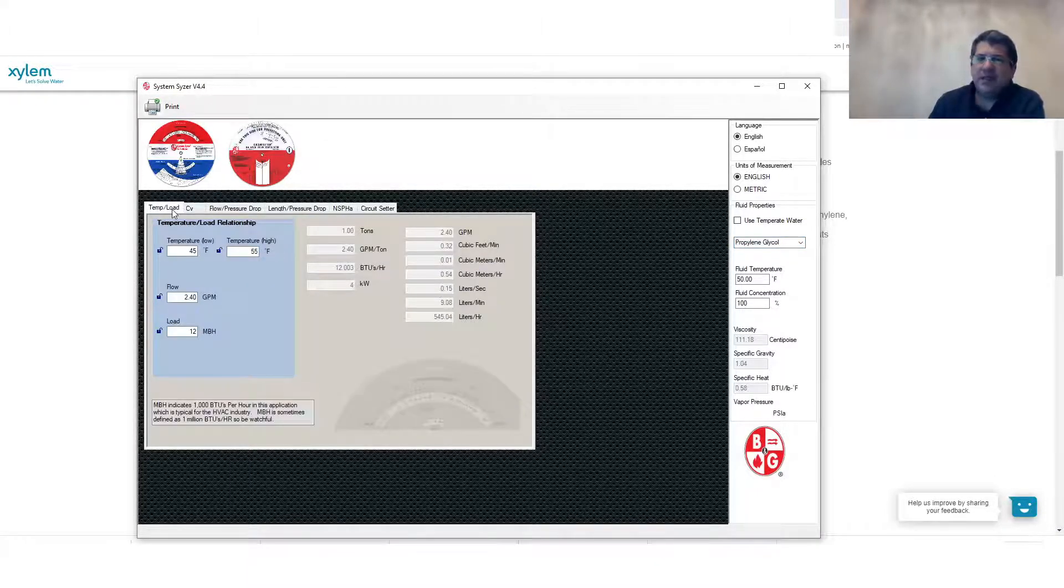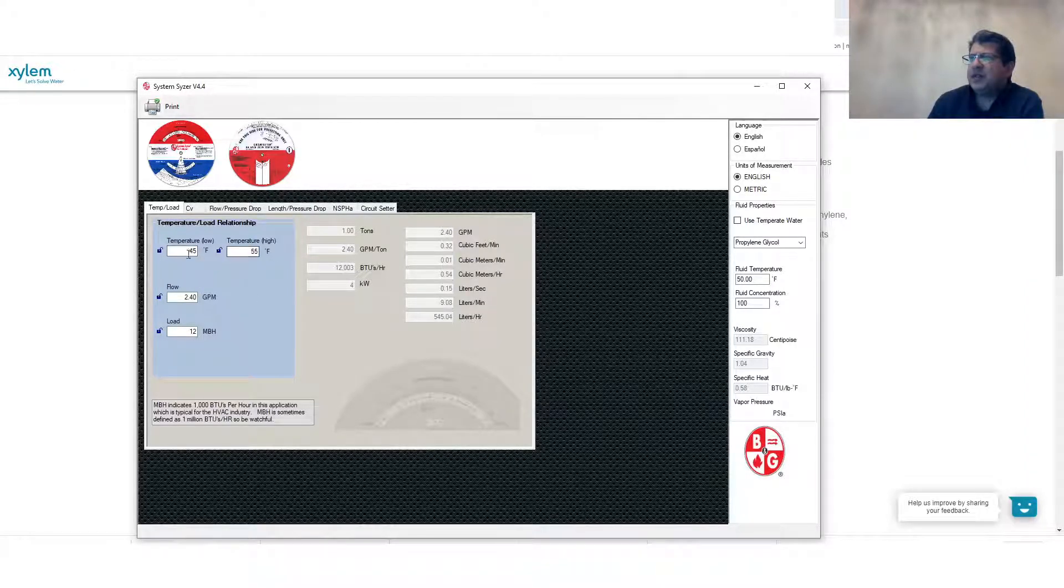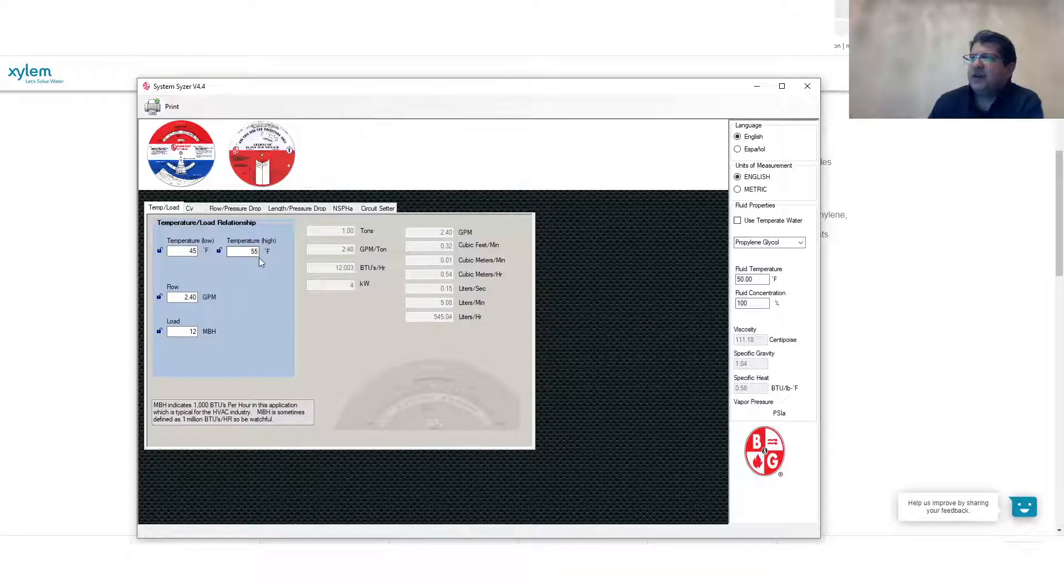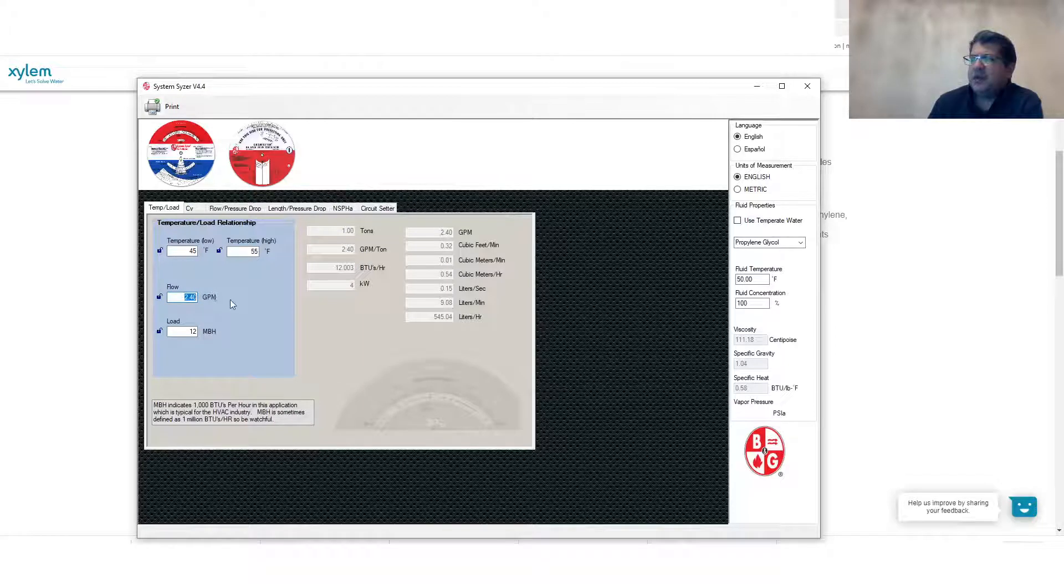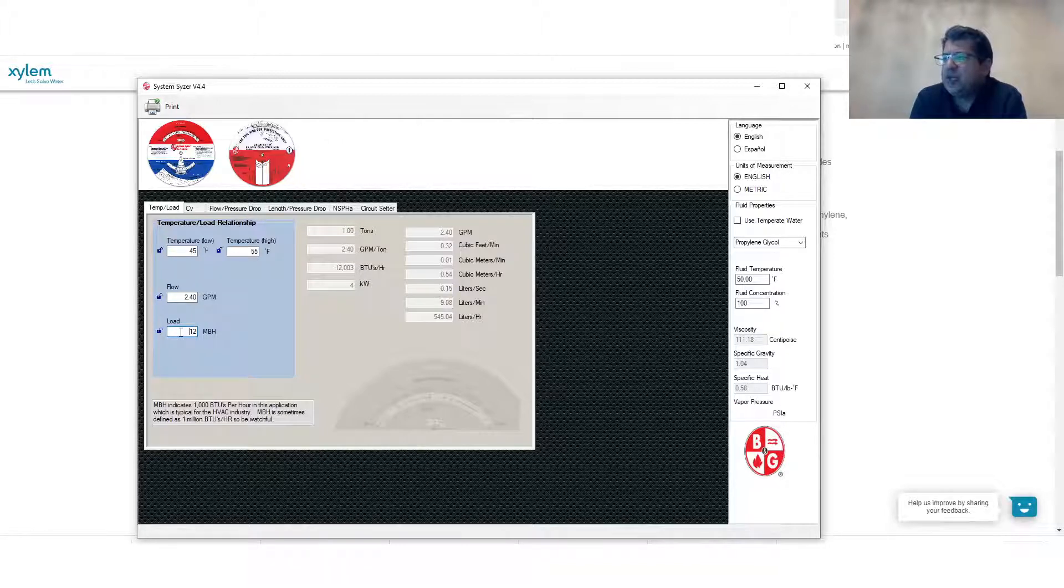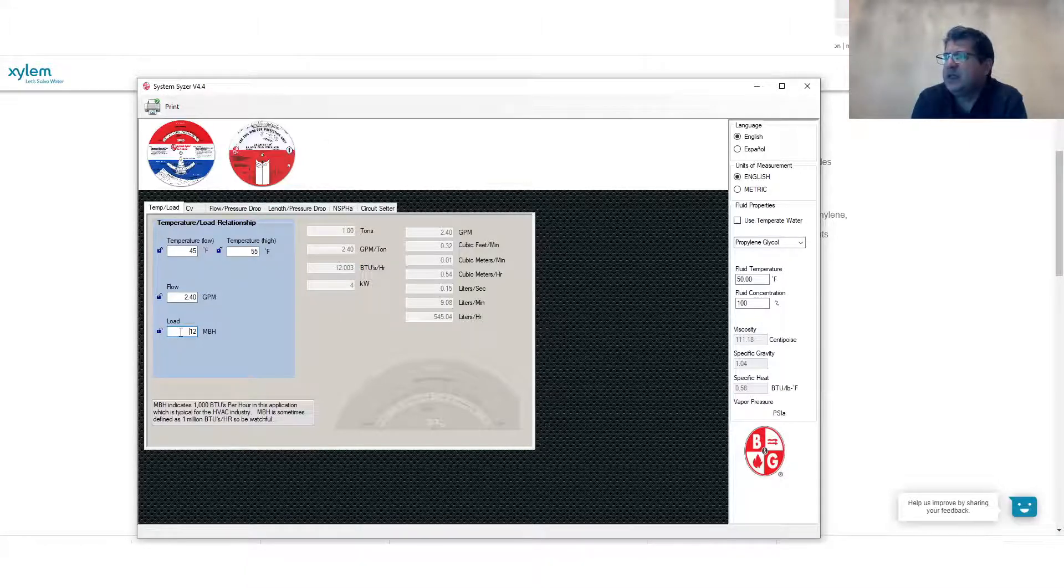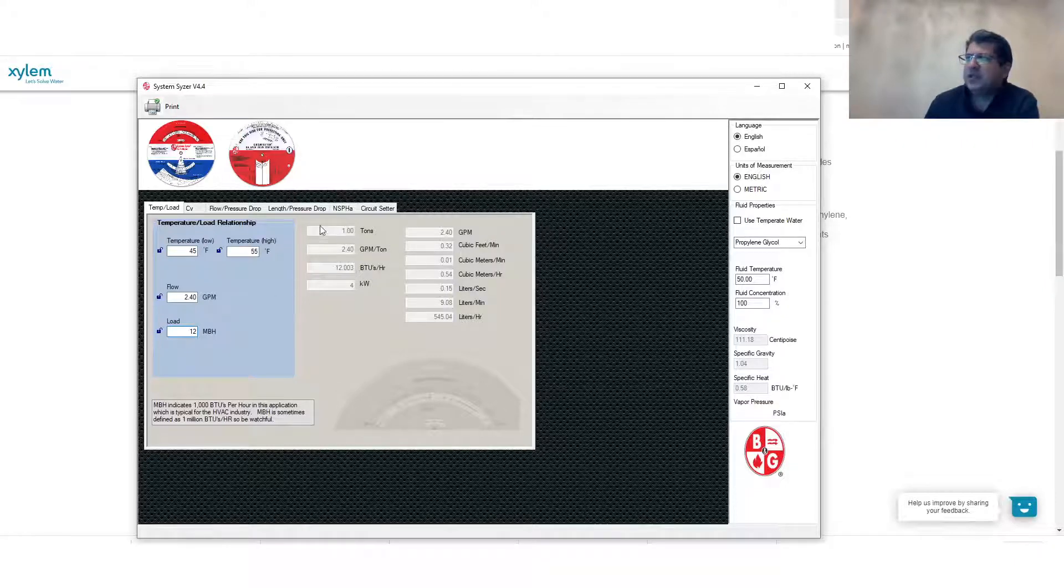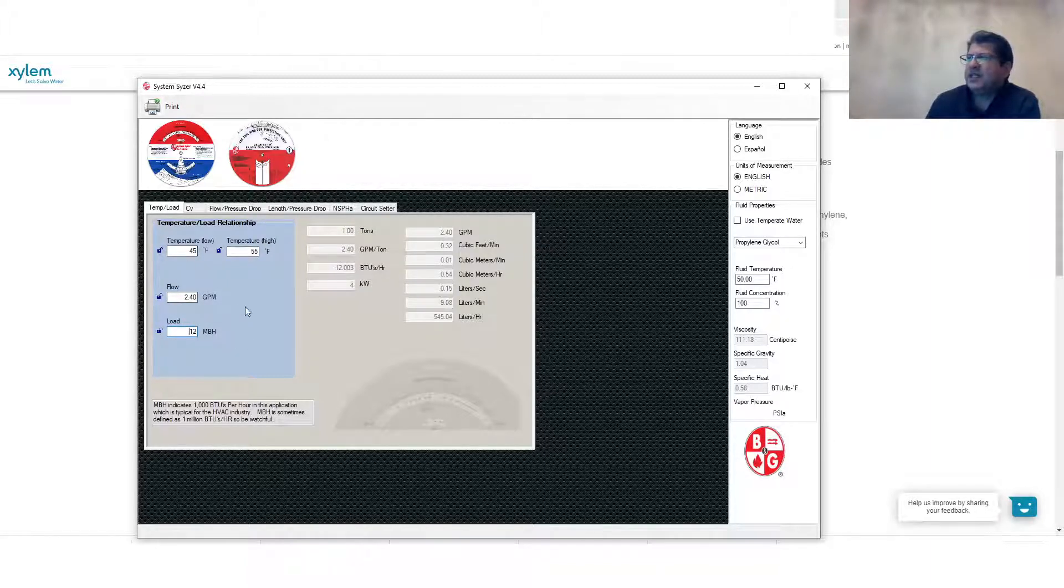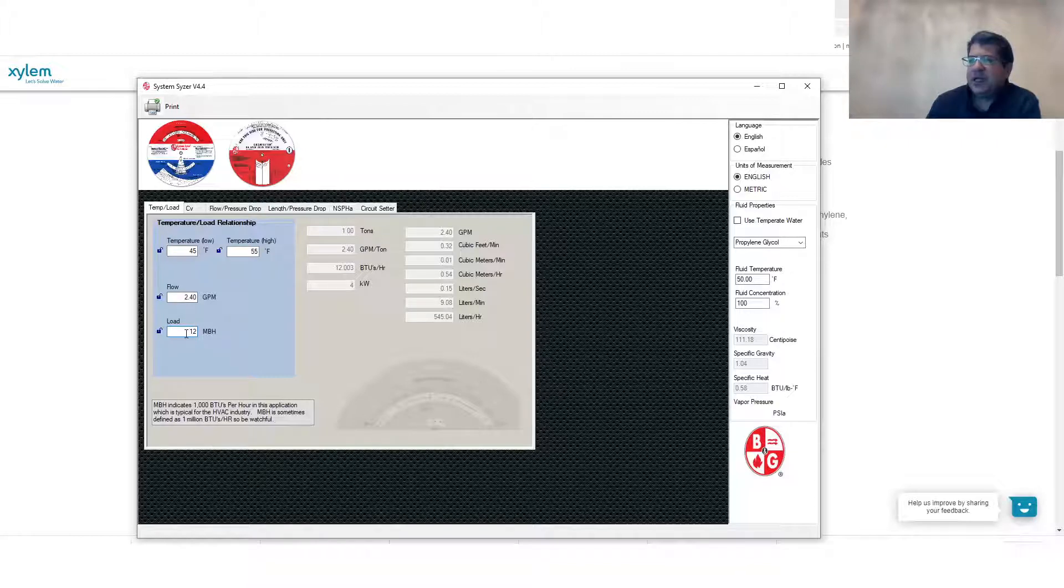When you have say propylene glycol chilled water, there is a different characteristic of absorption of heat and rejection of the heat. These can all be calculated based on the design you're taking into account. Going back to the left hand side when you look at the temperature load, you can easily provide a range of temperature. For example, if you have a chilled water ranging from 45 degree to 55 degree and a flow rate of 2.4 GPM, you would see that heat absorption can be close to 12,000 BTU per hour or 12 MBH. This is equivalent to one ton of cooling as you can see on the top right hand side.